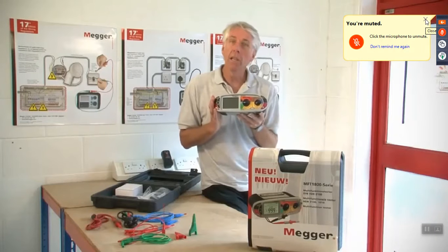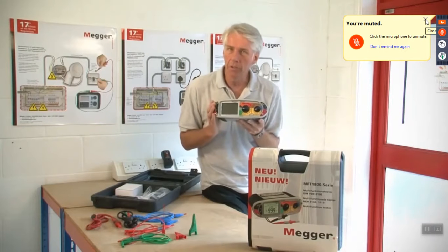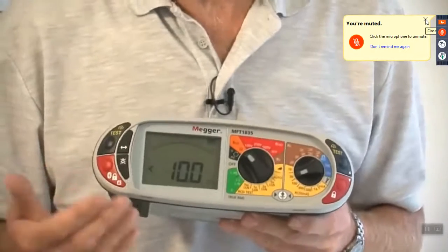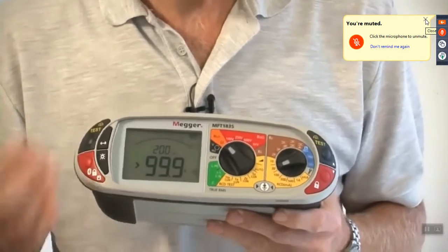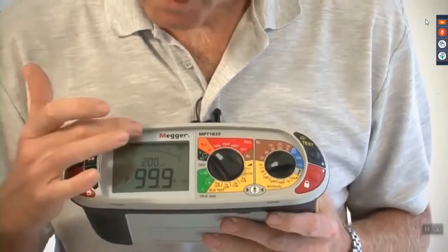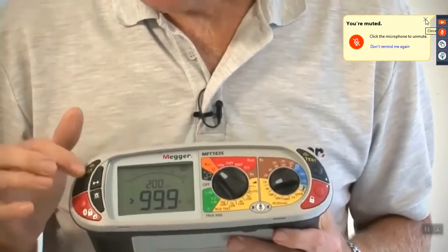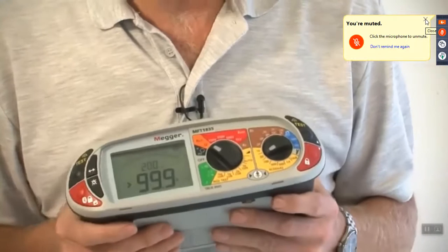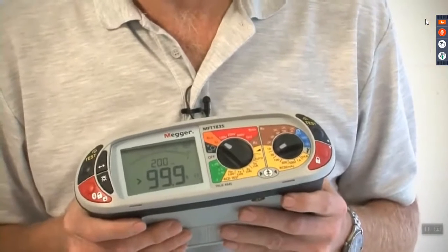Just like many other Megger products, the MFT 1800 series is category 4 safety rated and has a bulletproof input protection system. So even mid-test, if you apply voltages, it will not damage the instrument. We have a large dual function display, so when carrying out continuity testing, for example, the test current can be displayed at the same time as the resistance result. It has left and right-handed operation on all models, making it easier to use, and the MFT is also extremely tough, and it's IP54 rated as well.